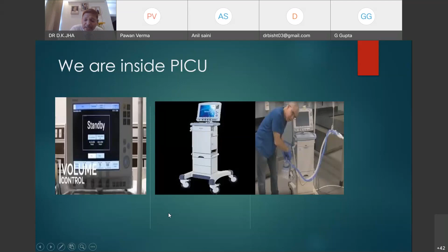So what should be the initial ventilator setting? My dear friends, the initial ventilator setting depends on which mode you are using. In volume control, tidal volume in smaller children should be set at 5 to 8 ml per kg. This is ml, not mi, it is a mistake. In older children, this is 8 to 10 ml per kg. There is a universal acceptance that if you don't remember age-wise, just remember that in any group of children, 5 to 7 ml per kg is the set tidal volume.